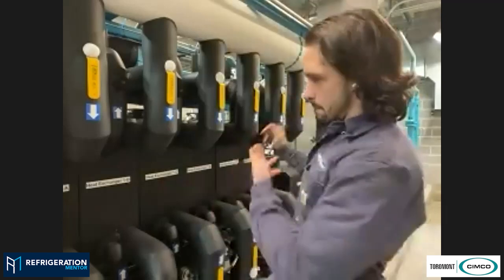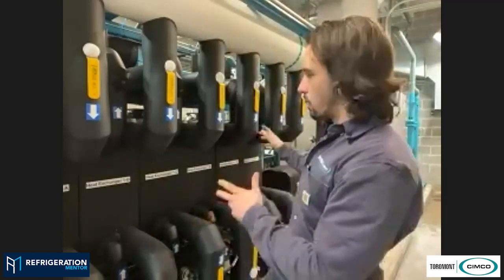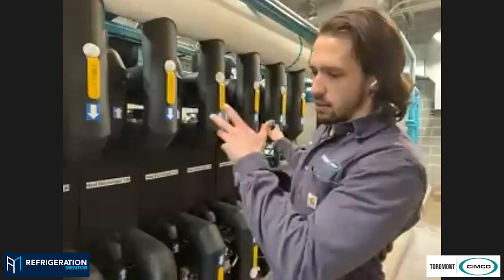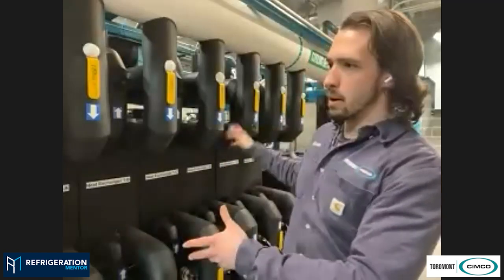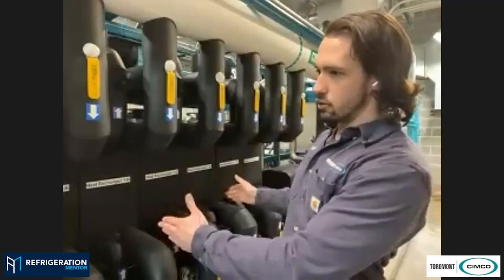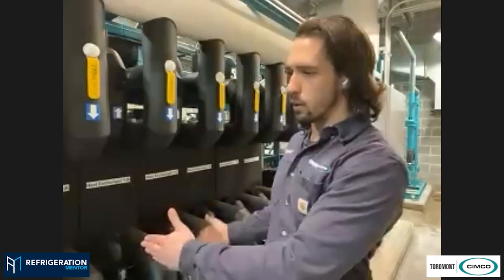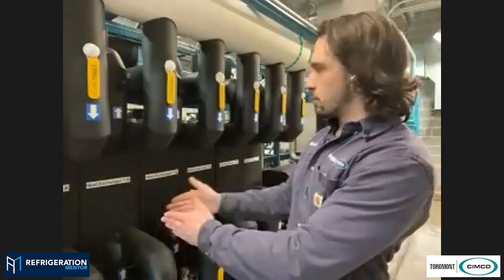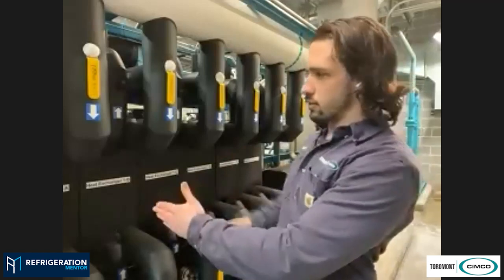Based off of deviation from set point is how many exchangers we'll bring on. So the pump will be enabled when the slab temperature calls for it, but based on how many degrees away from our return glycol set point we are, will enable the amount of exchangers and subsequent compressors.